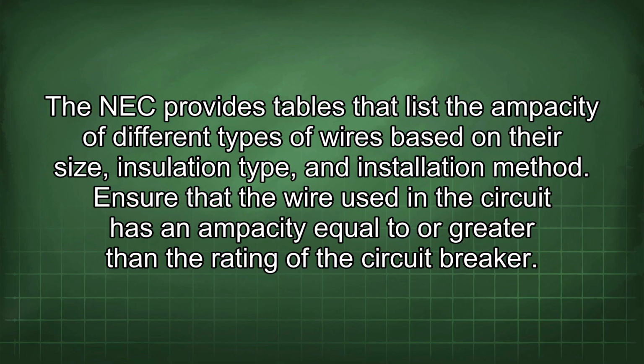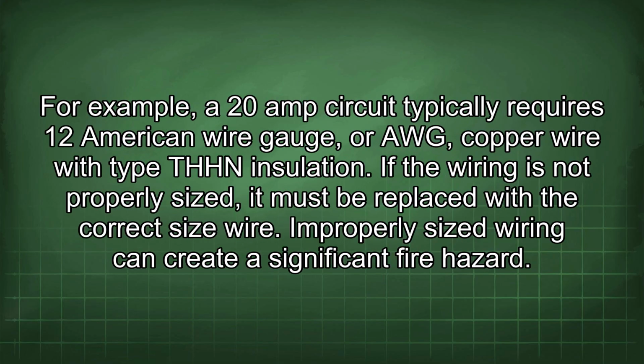The NEC provides tables that list the ampacity of different types of wires based on their size, insulation type, and installation method. Ensure that the wire used in a circuit has an ampacity equal to or greater than the rating of the circuit breaker. For example, a 20 amp circuit typically requires 12 American wire gauge, or AWG, copper wire with type THHN insulation. If the wiring is not properly sized, it must be replaced with the correct size wire. Improperly sized wiring can create a significant fire hazard.